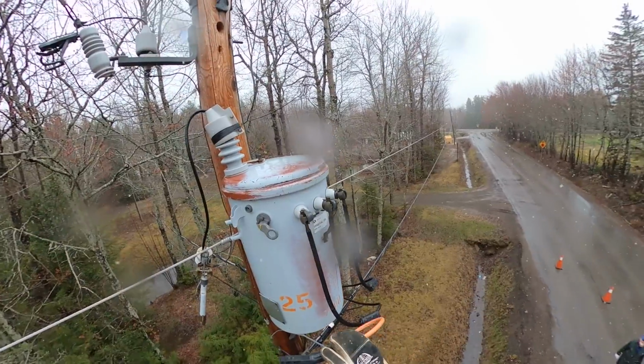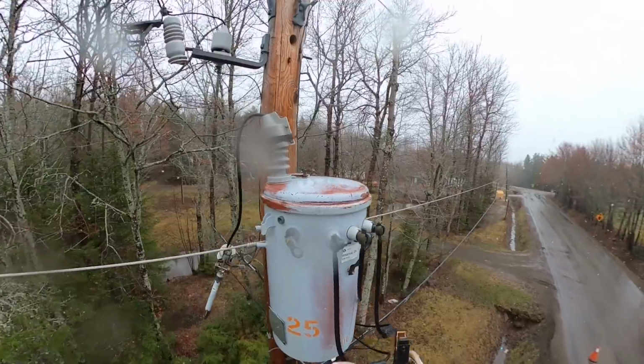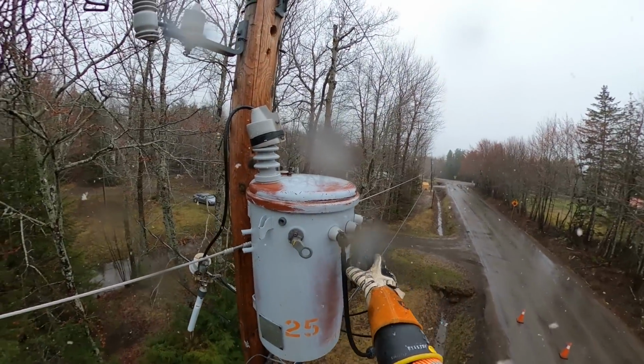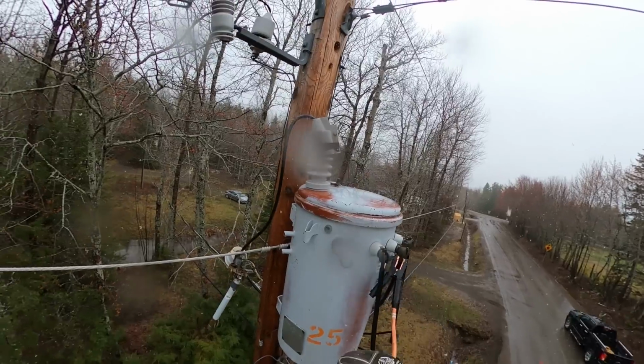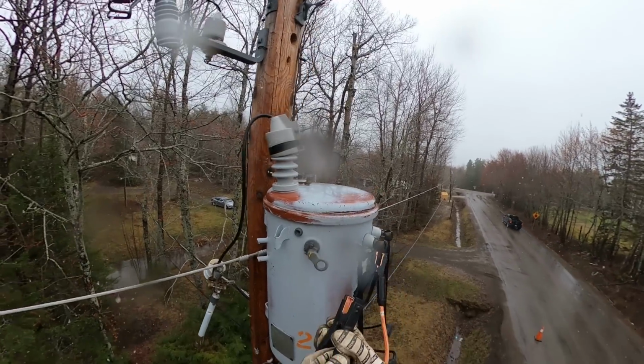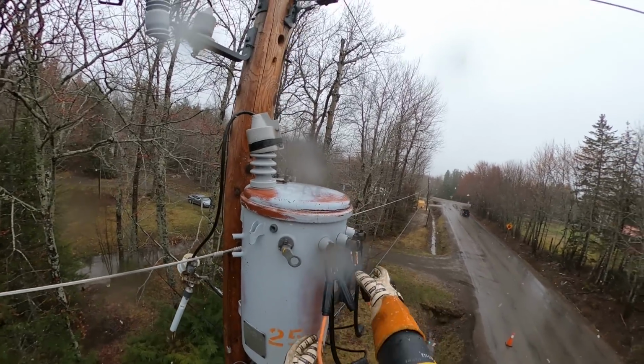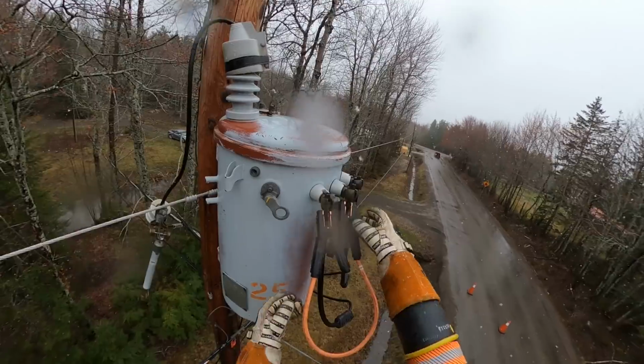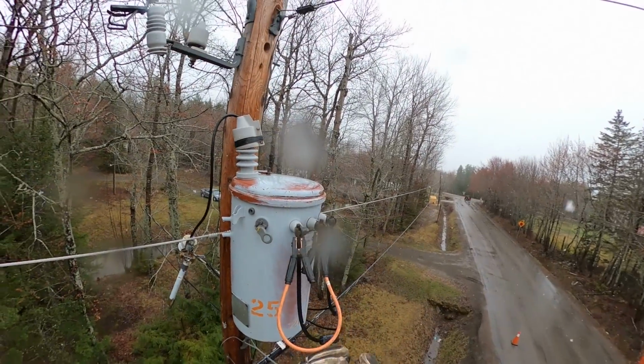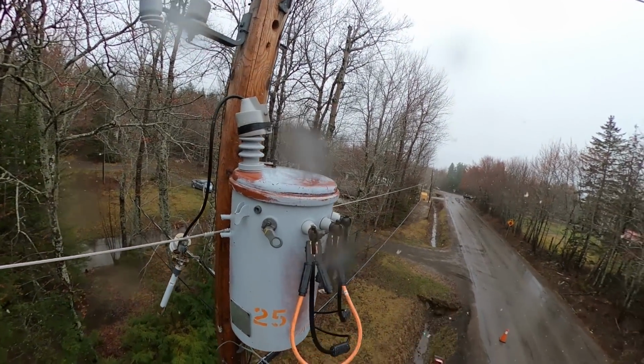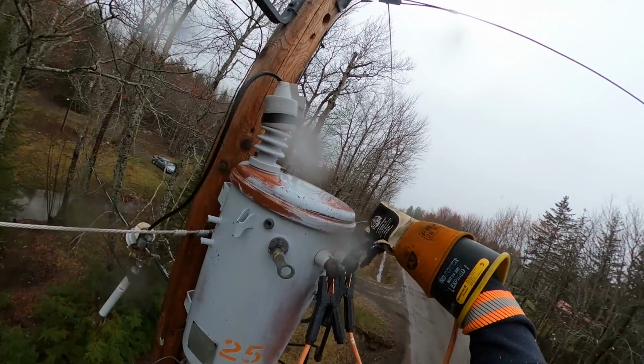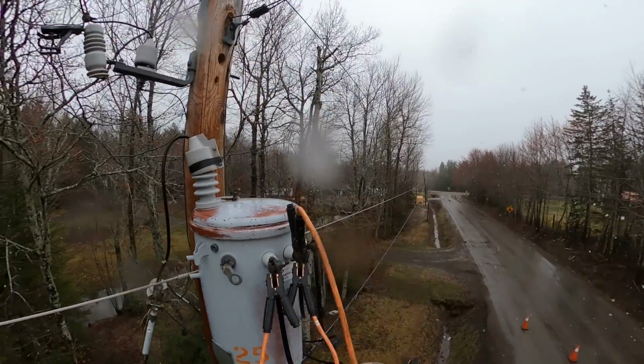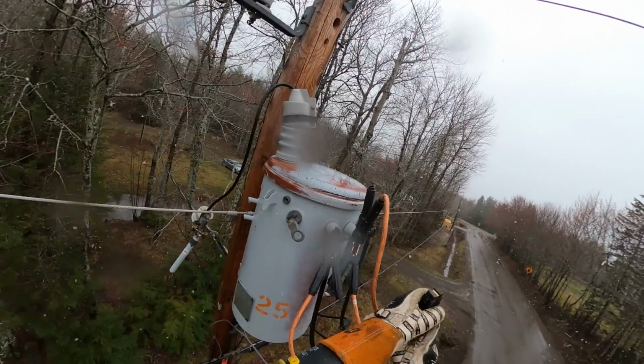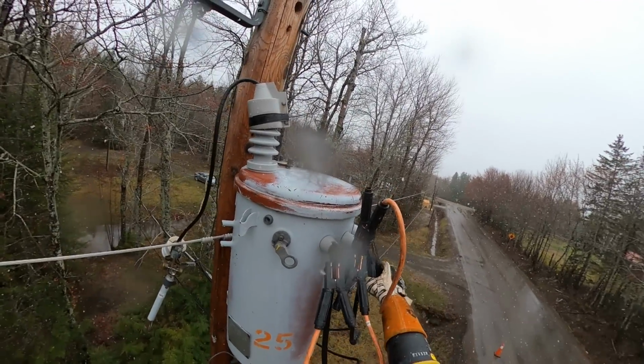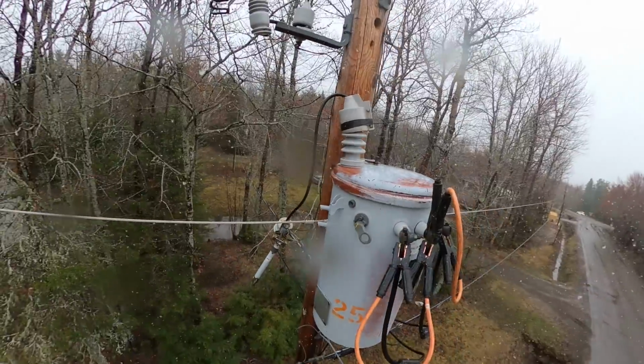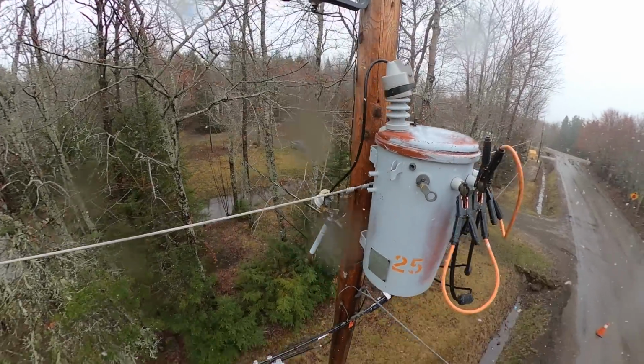Another step we want to do is eliminate any back feed. It's only affecting a single house, and I don't hear a generator or anything, but part of our procedure is to 100% eliminate that chance of back feed. So we have a few options: we could go to the house and remove the meter, or remove the secondary leads from the transformer. Probably the easiest option, we're just going to install a set of secondary grounds on the low voltage bushings of the transformer.